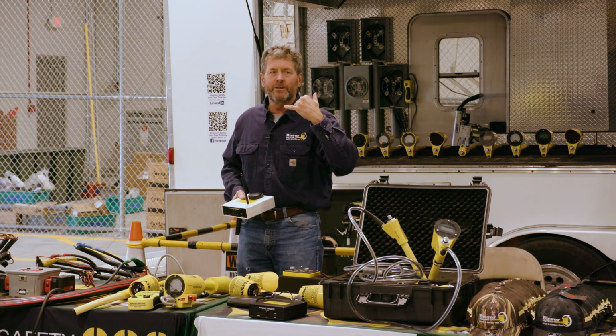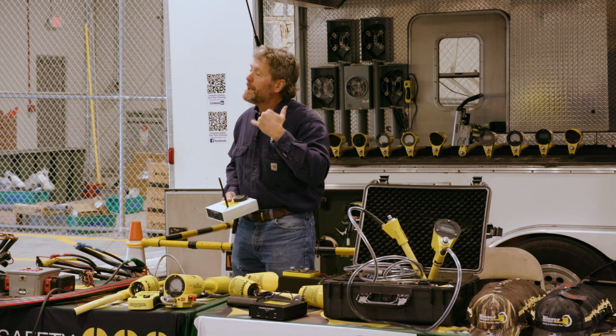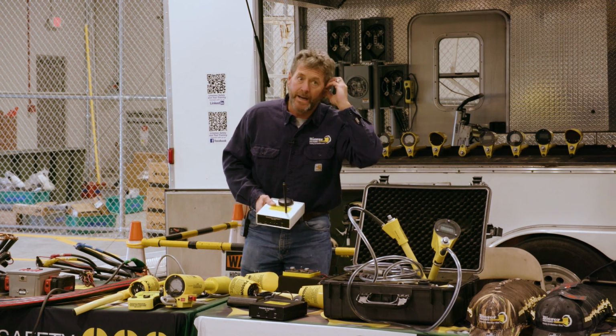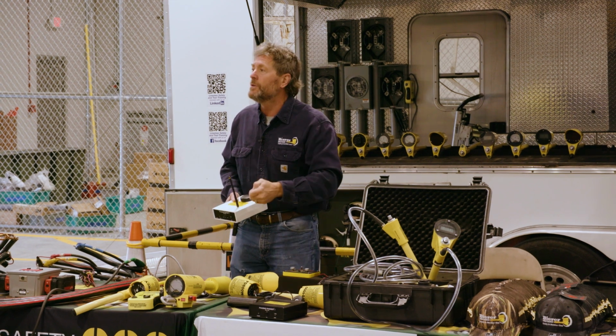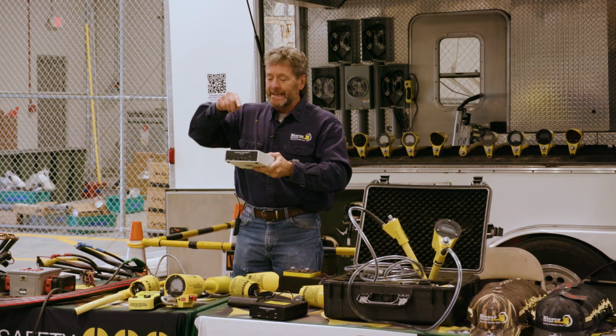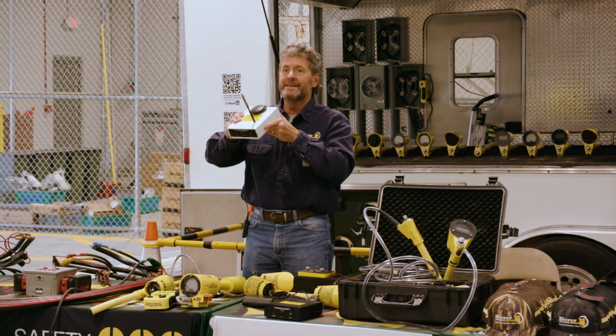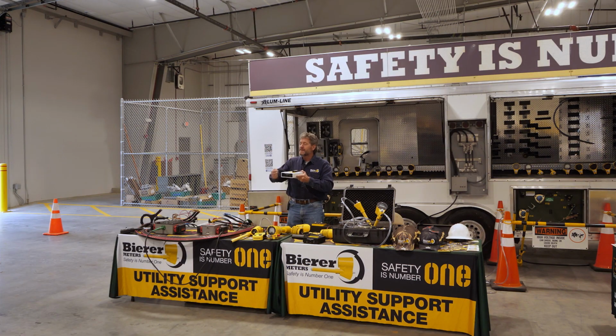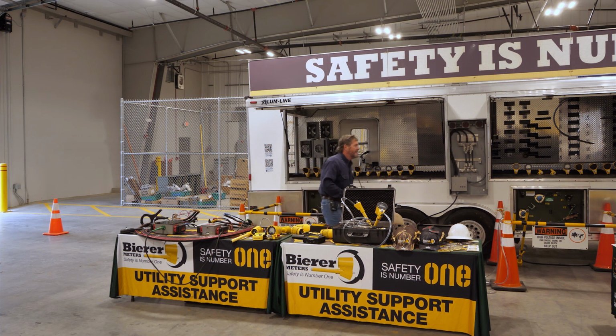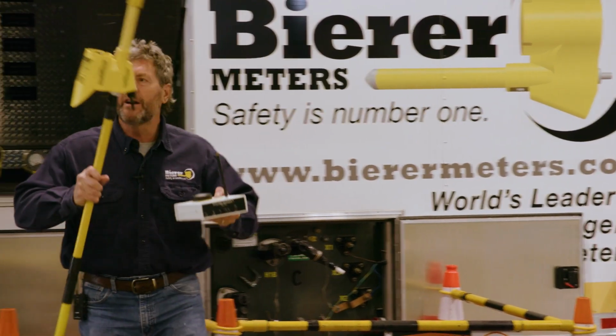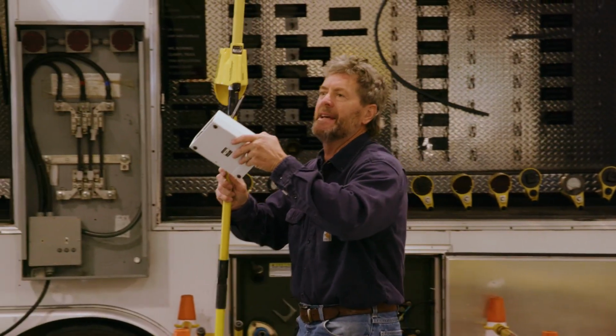You'll hear in your earpiece the grid data, beep beep beep, like that. And then you simply turn on your Bluetooth. When you turn on the Bluetooth, it links up to your field unit, and when it does, there's a white light here that goes solid. When the white light is solid, this becomes your A phase reference anywhere in the field. So when you're phasing, all you need to do is be within 300 feet of this antenna and this antenna.